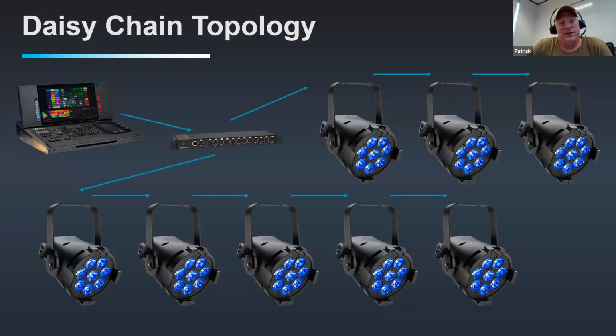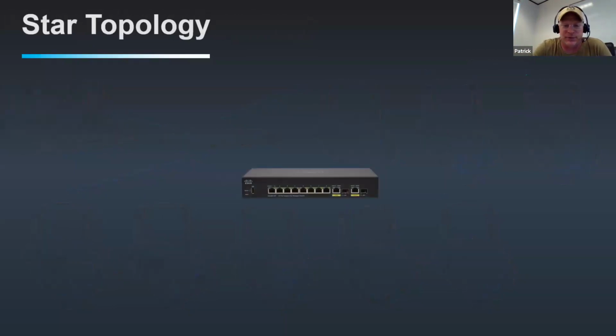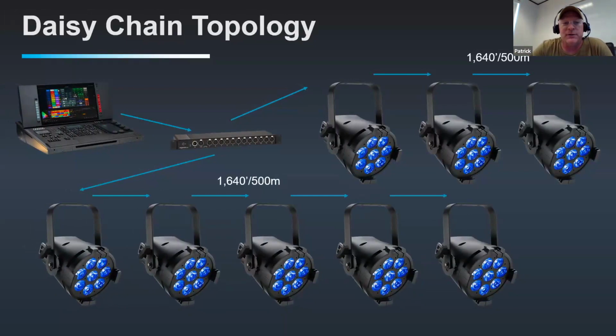Now the question is, what are our link limits? We can go 1,640 feet from the transmitter to the optosplitter, and then an additional 1,640 feet with 32 devices on each of these output lines. So we can now cover a pretty significant distance. We've got 1,640 feet, and what's missing over here is an additional 1,640 feet.